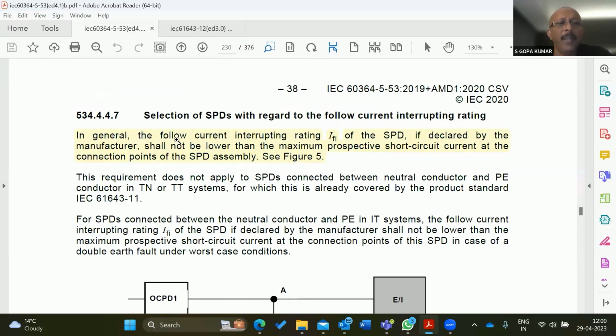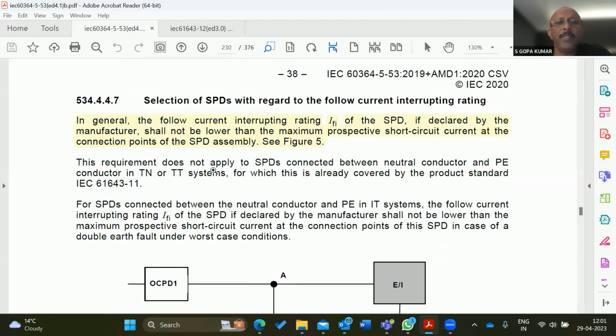The second one: in general, the follow current interrupting rating of the SPD, if declared by the manufacturer, shall not be lower than the maximum prospective short circuit current at the connection points of the SPD assembly. This is applicable for a spark gap based SPD. In a spark gap based SPD, there is a parameter called follow current. The follow current rating has to be at par with the short circuit level. Here also, we are finding in several cases, the follow current rating of the SPD is 25 kiloampere and the short circuit rating of the panel is 50 kiloampere. So these are actually dangerous.